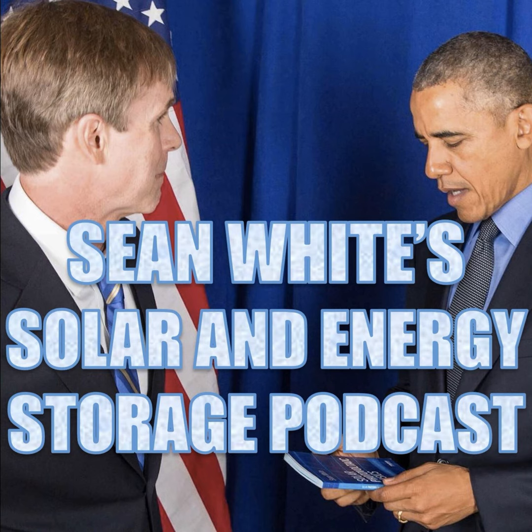So now, what is the maximum voltage of an ESS? It would be the rated input and output voltages on the nameplate, so look on the label - it'll tell you what can come out of that thing. Remember, an energy storage system is not just a battery. It has electronics that can control things like voltage and current.